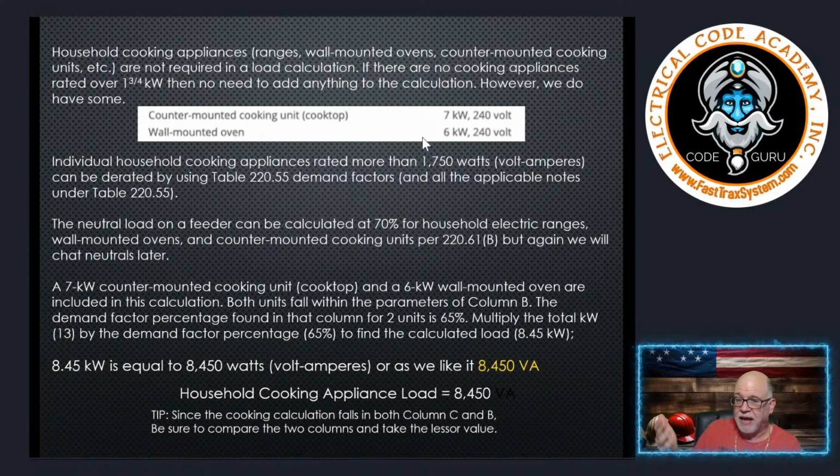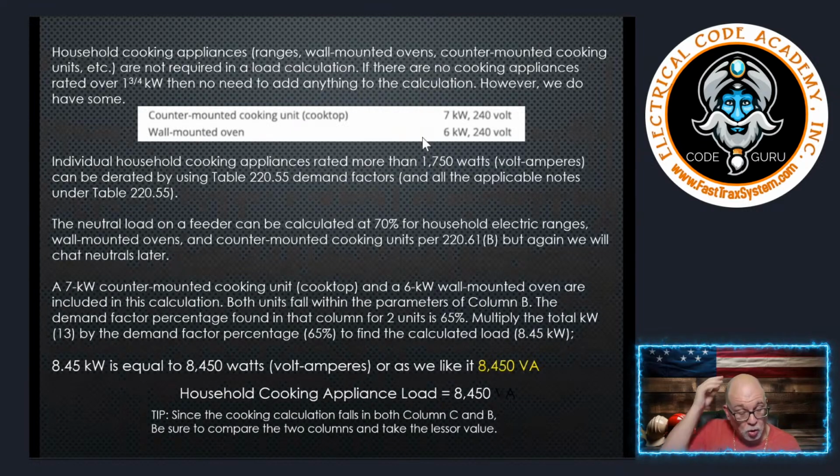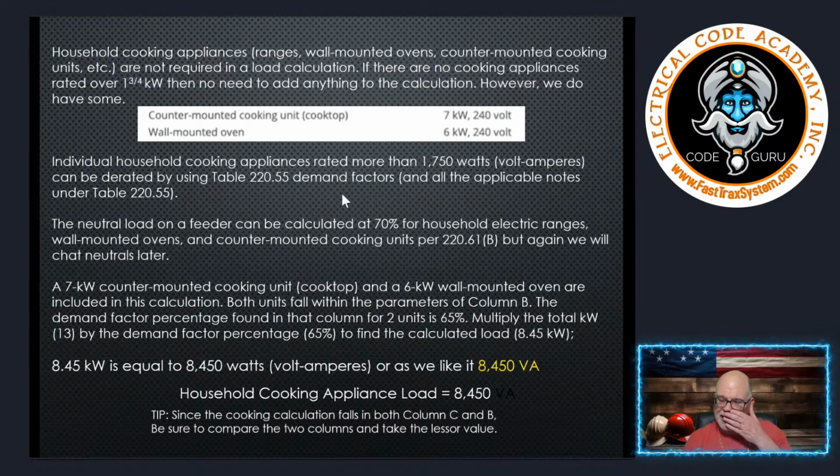Okay, whatever it is, you just don't get to apply any demands to it. All we're talking about is, can we apply any demands? But in our case, all of ours are over 1 3/4. So we're going to be able to apply some demands here.